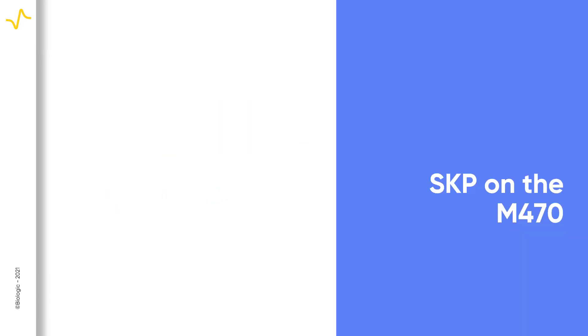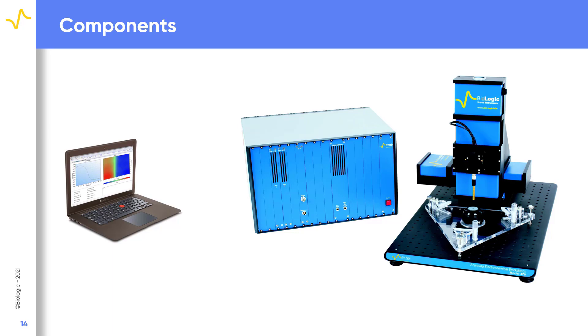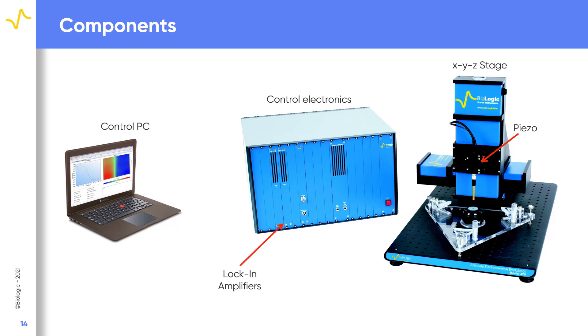So how is SKP implemented on the M470 with the SKP 470 module? The components used to perform SKP measurements on the M470 are shown. A control PC runs the M470 software, which interfaces with the instrument to set up and run the SKP experiments. The control electronics interface between the software, computer, and the various electronics required by the system. An XYZ scanning stage allows the probe to be approached to the sample in Z, follow sample topography if desired, and raster scan the surface in X and Y. These are automated to allow area maps of the contact potential difference to be produced. A piezo vibration actuator is required to vibrate the probe at known, repeatable amplitudes throughout the measurement, resulting in an AC signal which is then demodulated by the lock-in amplifiers.